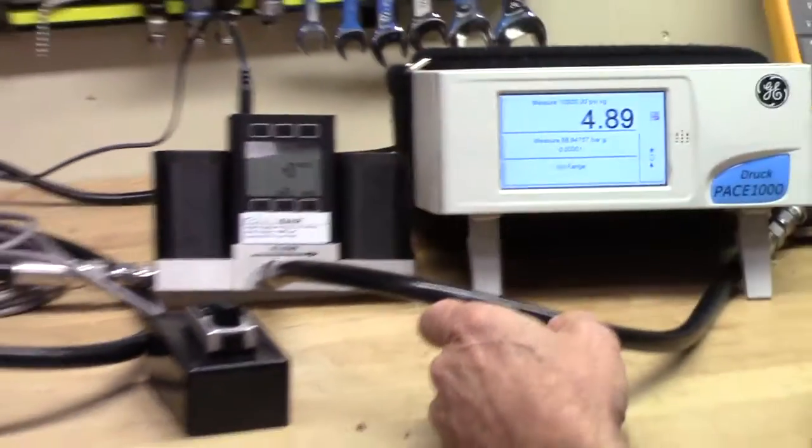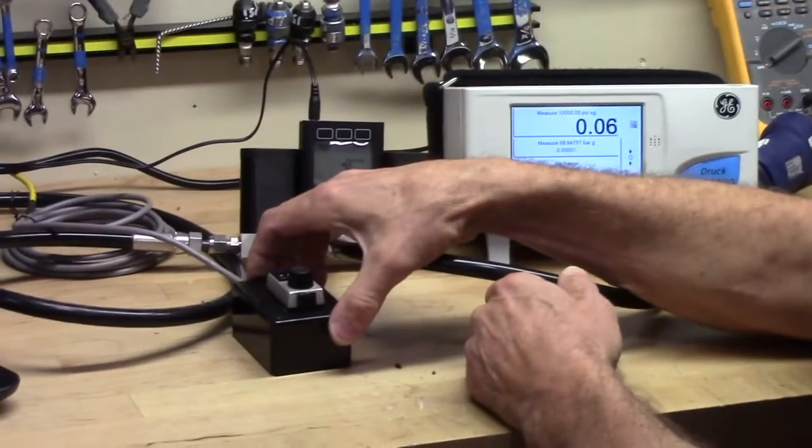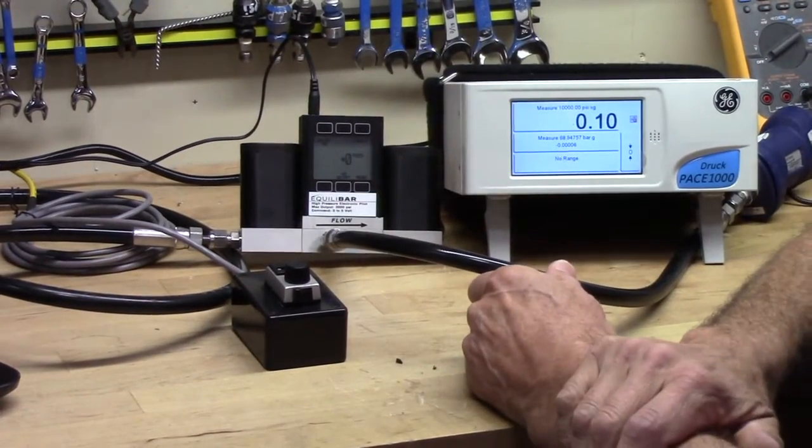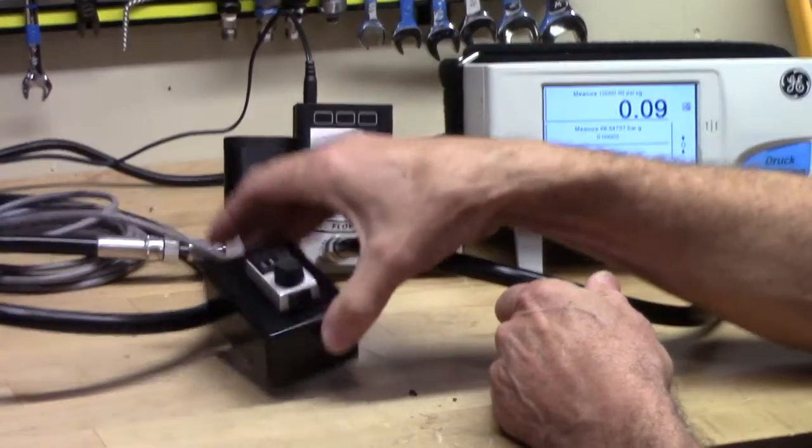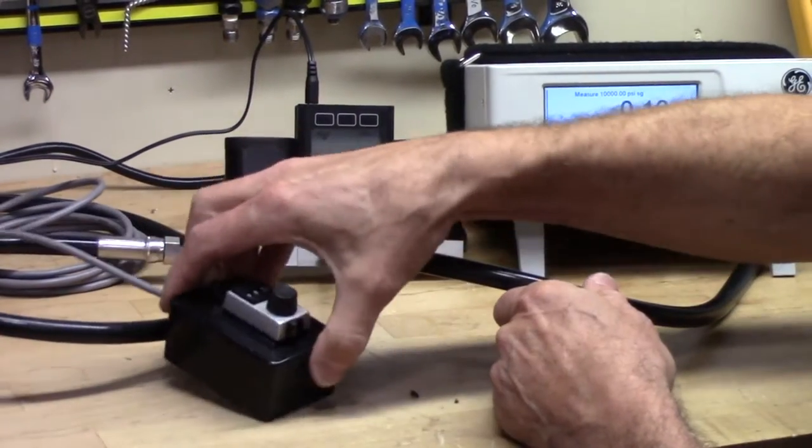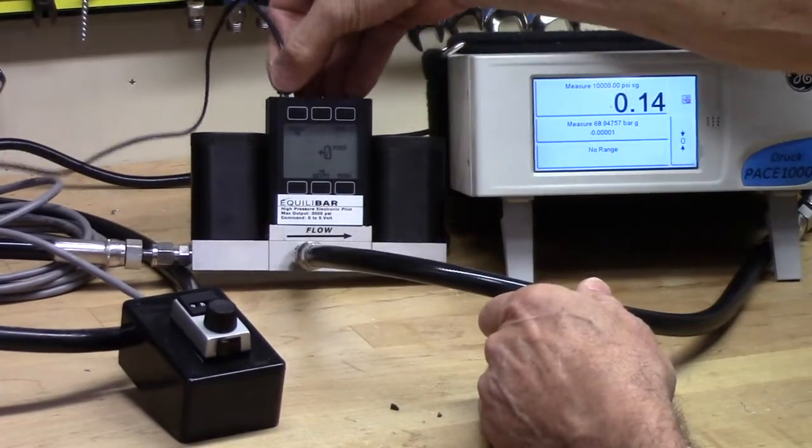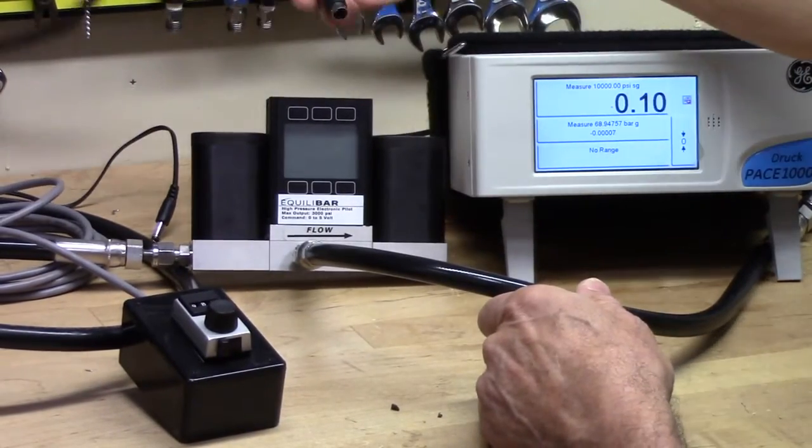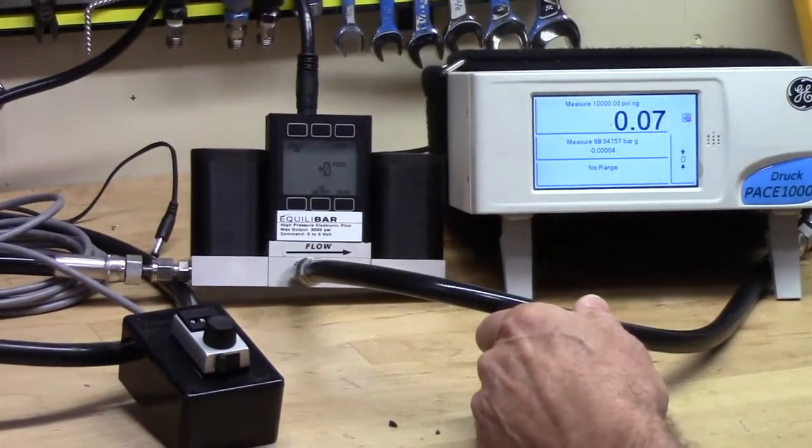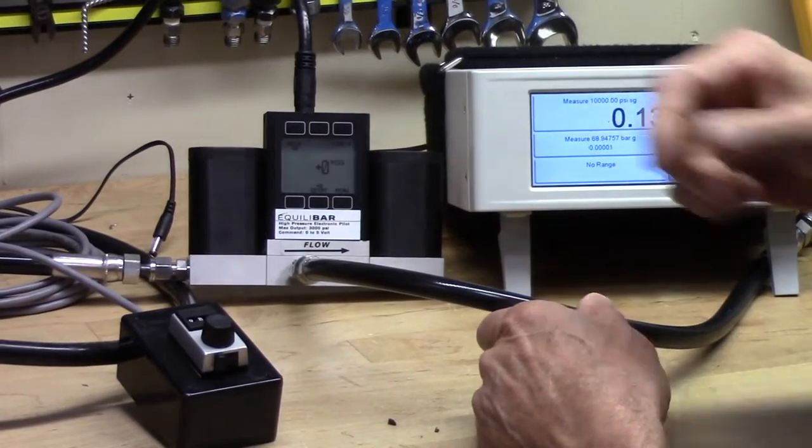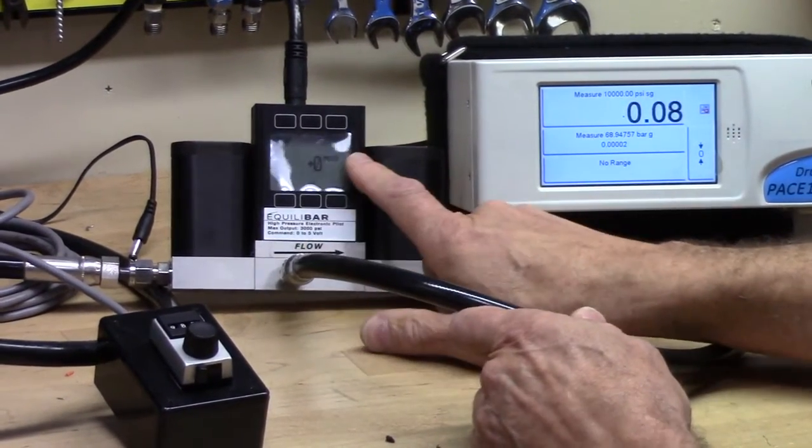The second method for controlling the set point of EPR 3000 is through the analog signal zero to five volts DC through pin four of the mini DIN connector. To simulate actual environment we're going to be using this potentiometer that we can vary from zero to five volts. It is supplied through pin four of the mini DIN connector and in this case the power is also supplied through the mini DIN connector. Now we need to change the set point source from front panel to analog.